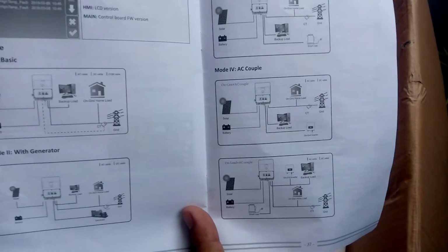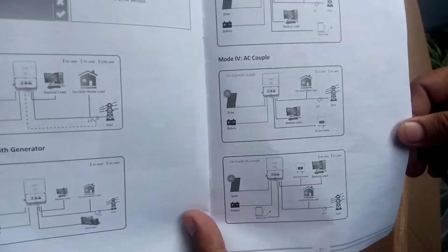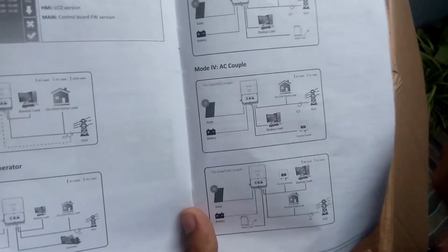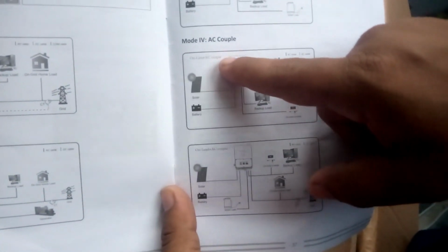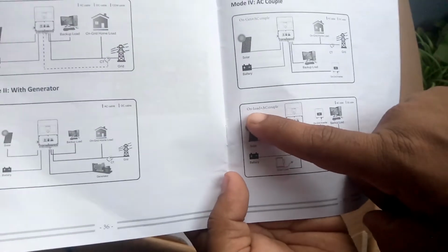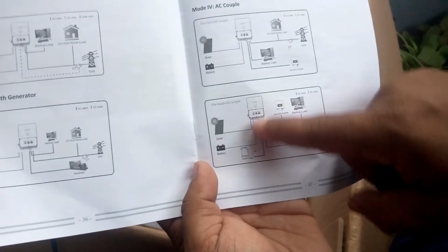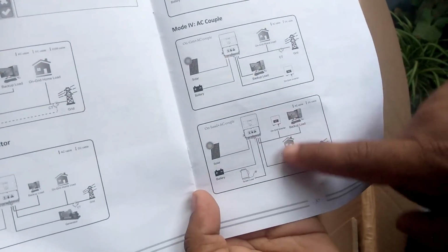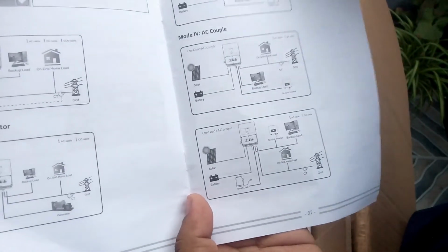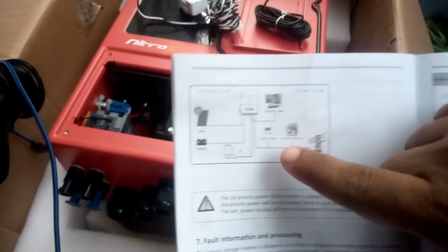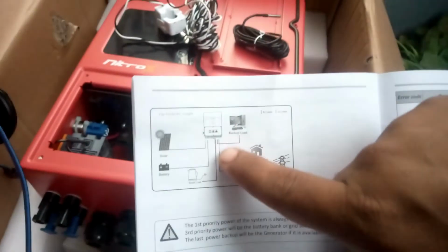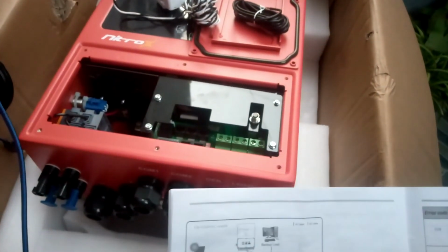Yes, and the fourth mode has further 3 options. For example, in the fourth mode we connect the generator port with the grid tie inverter. This is called on generator AC couple. On the generator we are coupling our grid tie. The second option is on load plus AC couple. In this we connect the smart load with the generator port and connect the inverter with the backup load. You can see the load connection of the backup load. And the third one, the difference is that we connect the grid tie inverter with the generator with the grid ports. Okay, this is the difference.